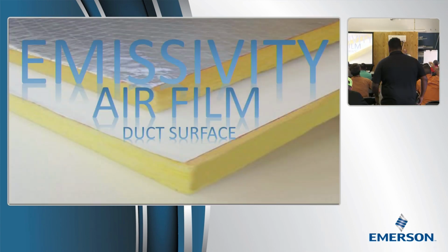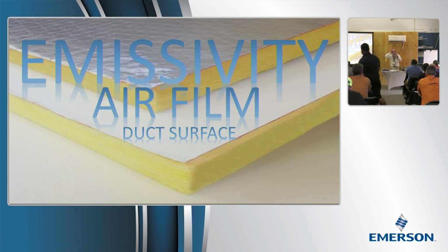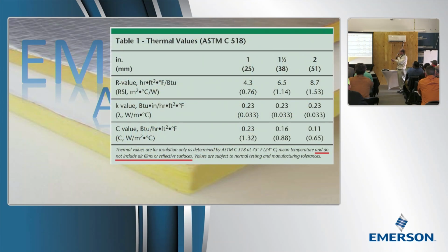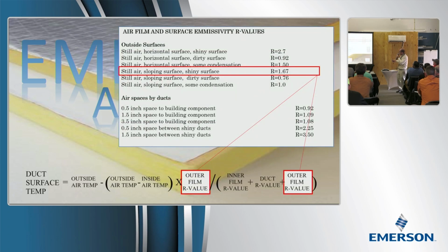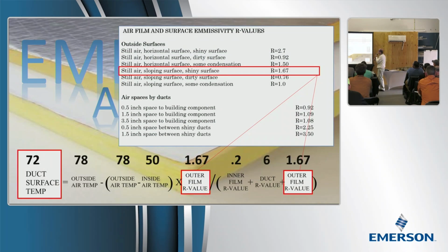Let's just explain the emissivity. Do we have infrared users here? You guys know about emissivity, because you know that when you point the camera at something shiny, you've got to change the emissivity rating. Well, that has to do with how much heat it puts off in the infrared range, which is also right where we are with sweating ducts. And so what that means is that if we work the formula that we've been doing here all day, we'll just go ahead and do it.